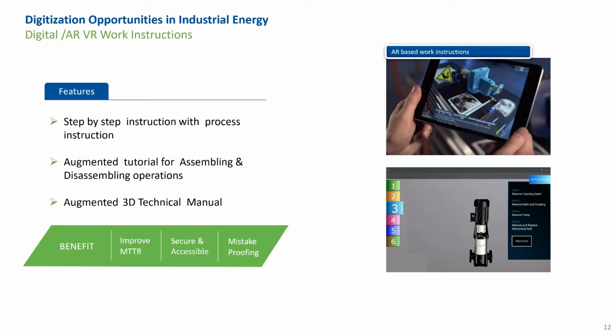Imagine virtual, easy to access reference manuals from the manufacturer of that relay with a click of a button. You can check a replacement parts inventory back in the spares shop because the relay is not testing good, or you can collect the testing information and download it live right there, then see trending with prior testing.